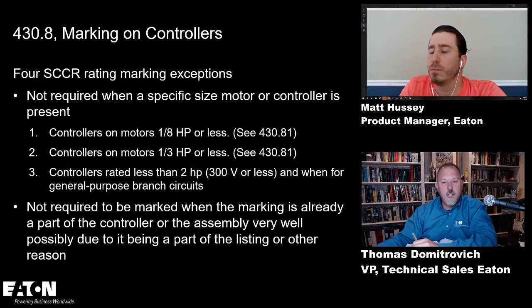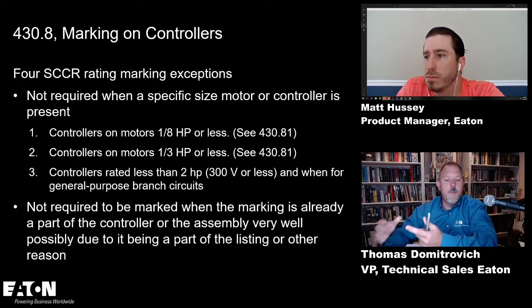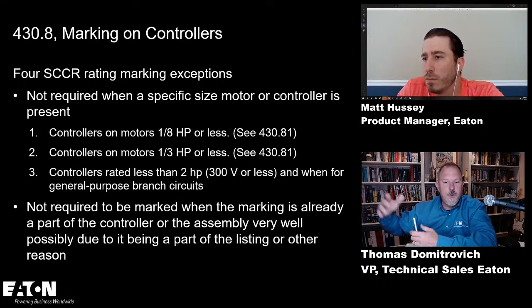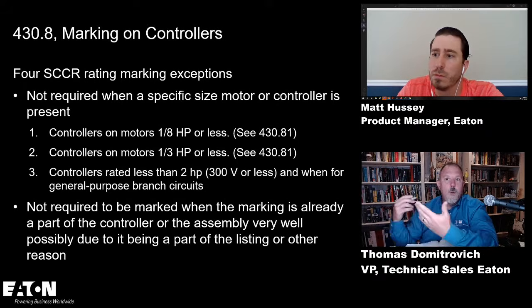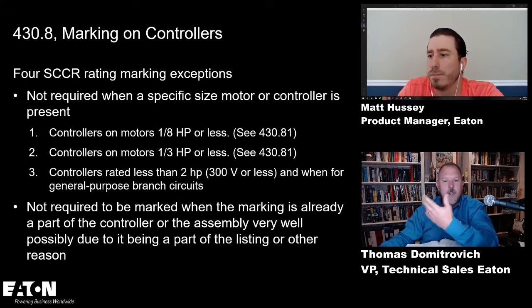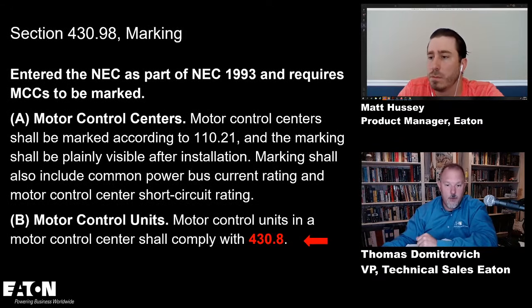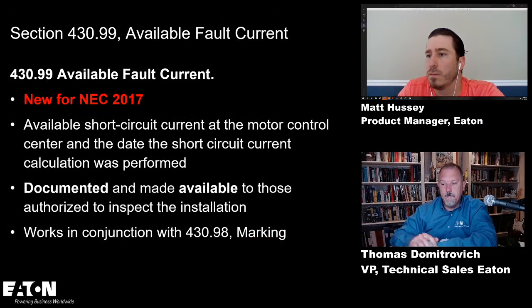They made some changes in the latest version of the code. They pulled some of it, which is really related to HVAC equipment, but in any case, it's not required to be marked when the marking is already a part of the controller or the assembly, which we already do. So you don't have to field mark these things. We already have all of that on the equipment. But they will have to calculate the fault current and make sure that it's being applied correctly.